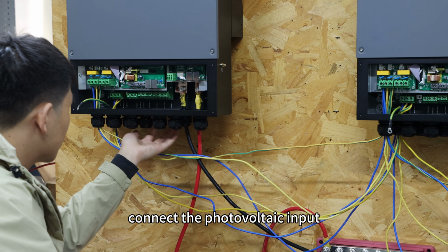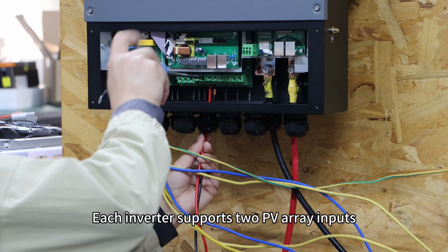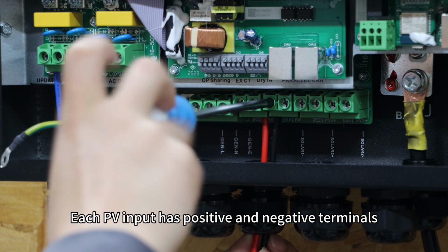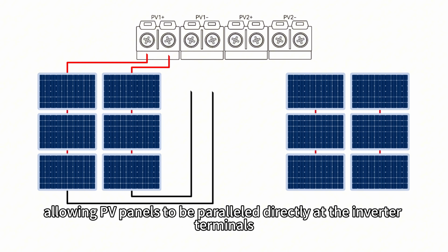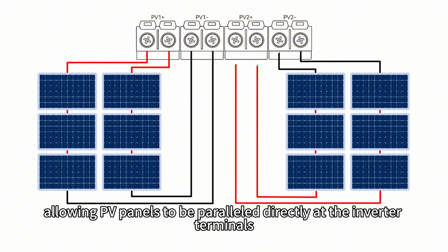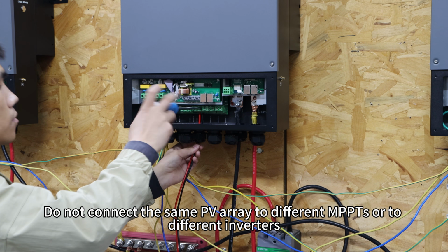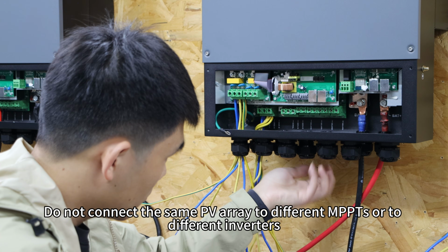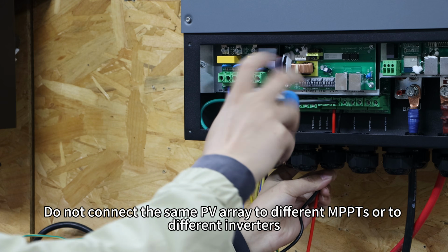Now connect the photovoltaic input. Each inverter supports 2 PV arrays inputs. Each PV input has 2 positive and negative terminals, allowing PV panels to be paralleled directly at the inverter terminals. Do not connect the same PV array to different MPPTs or to different inverters.